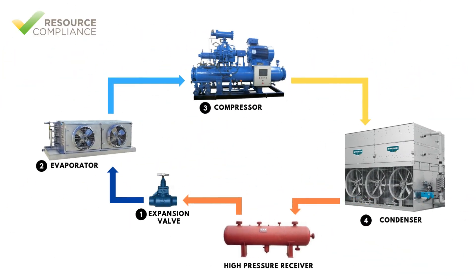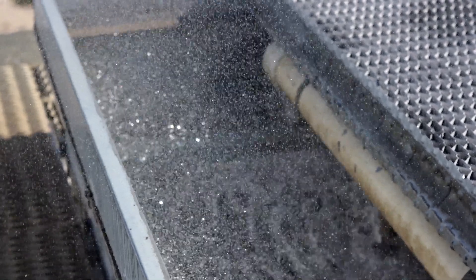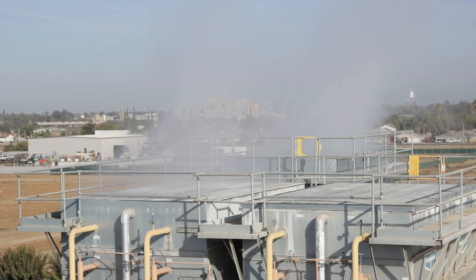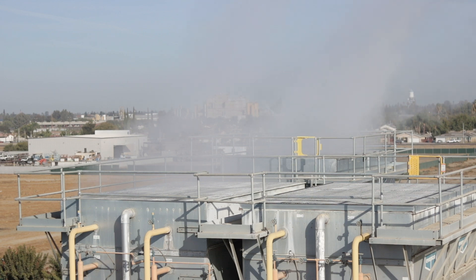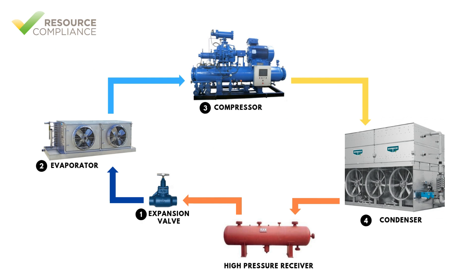Evaporative condensers receive high temperature superheated vapor from the compressor. The refrigerant cycles through the coils as water is sprayed over the coil surface and fans move air across the wetted coil surface. This process causes a portion of the water to evaporate, taking away heat from the refrigerant. This evaporation significantly enhances the cooling process by utilizing water's latent heat of vaporization. As heat is removed, the refrigerant condenses into a high pressure liquid, which exits the condenser and can be supplied to a receiver or expansion device for further use in the system.